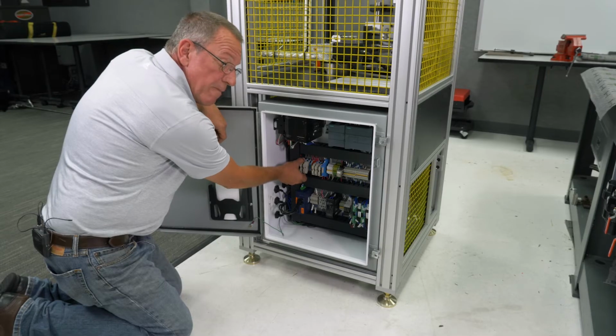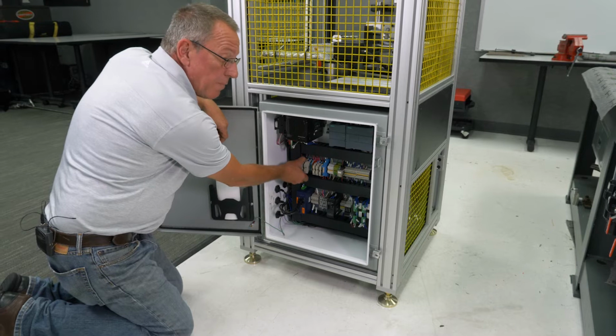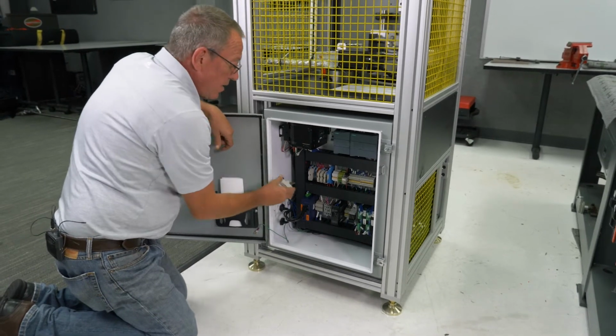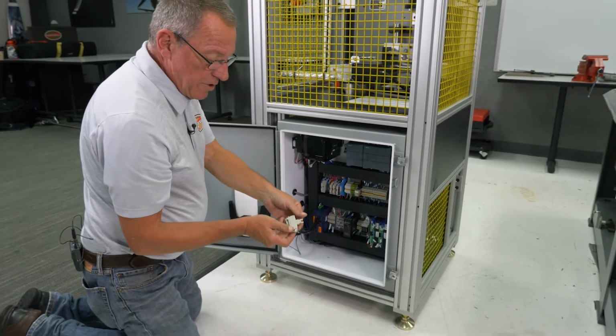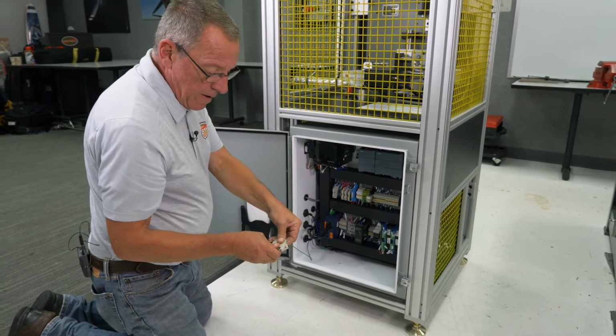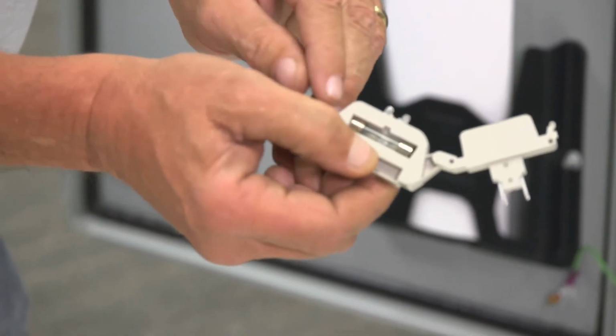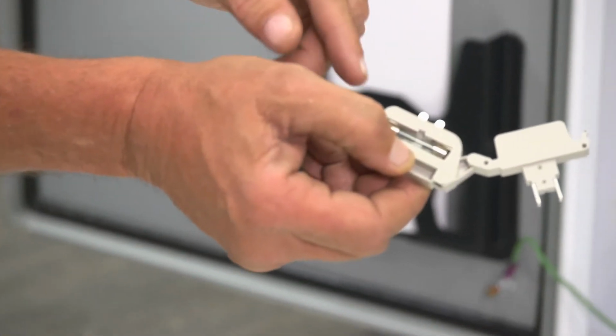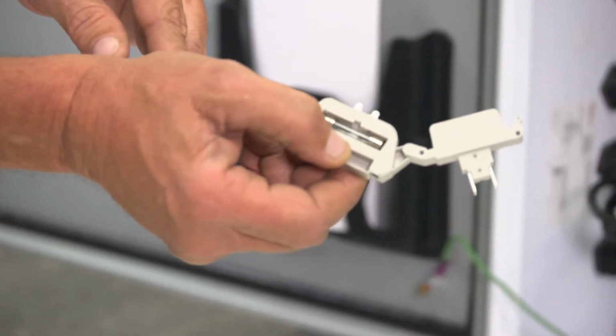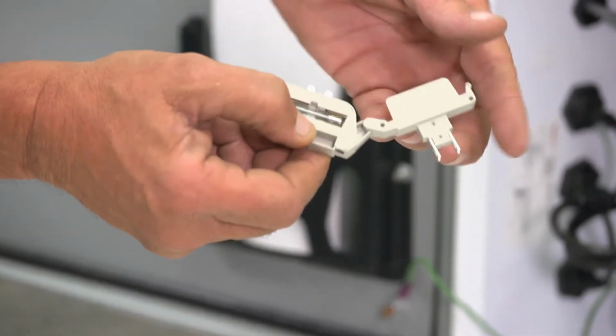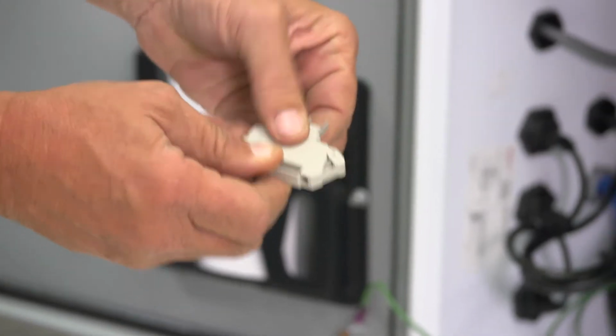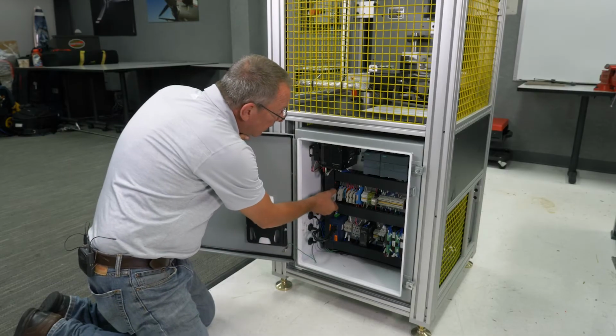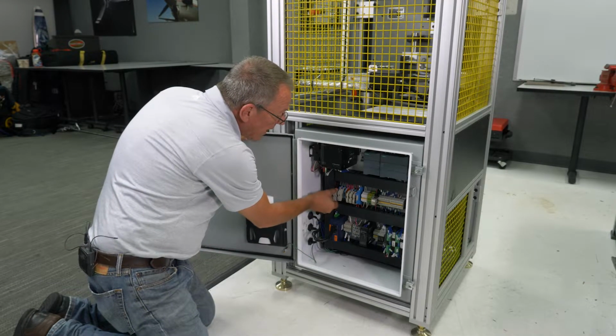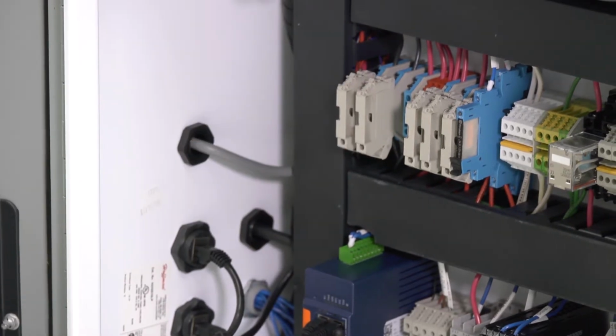If there's a machine malfunction of one type or another, it may be one of these fuses. And to check the fuses, just extract the fuse block and open it. There's a small bus fuse inside. You can check to see if the fuse is still good or not. Replace the fuse, close the block, and reinstall the block in its proper location.